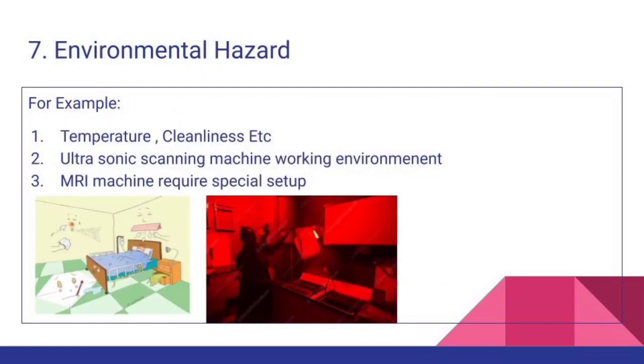The next is environmental hazard — for example, temperature of the hospital environment, ICU, or emergency sections; cleanliness around the hospital or patient rooms; ultrasonic scanning machines needing a special clean working environment; and MRI machines requiring a special setup with absence of metals.